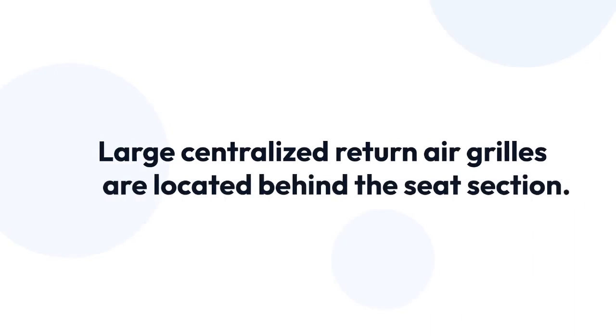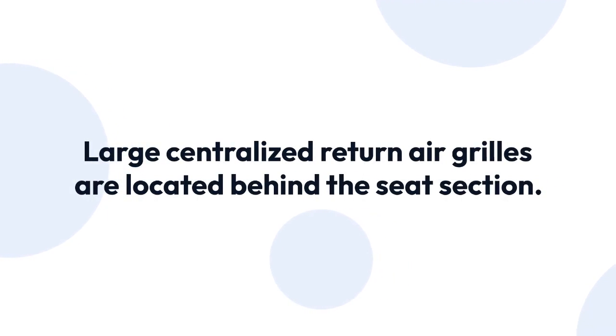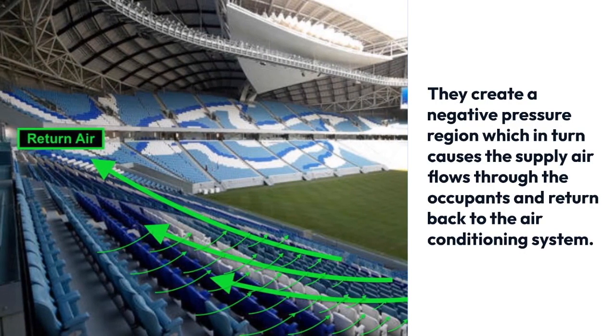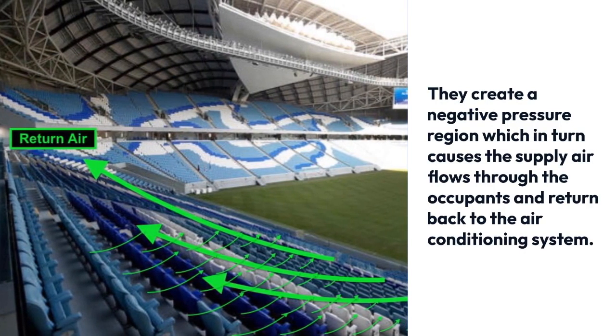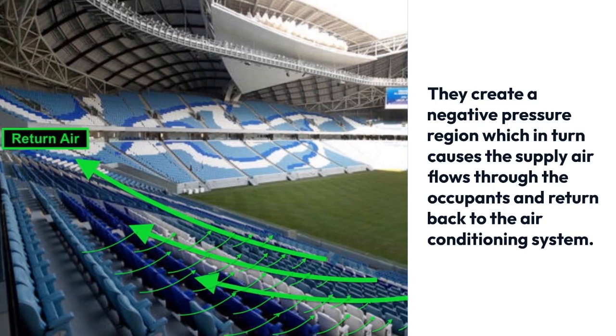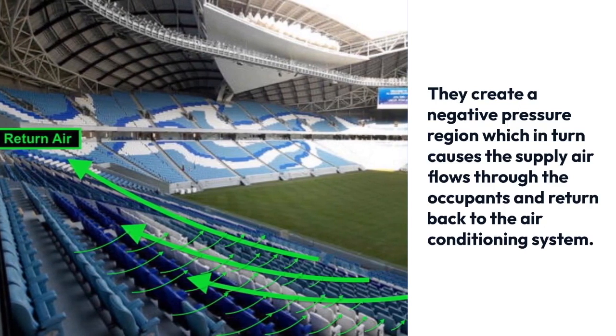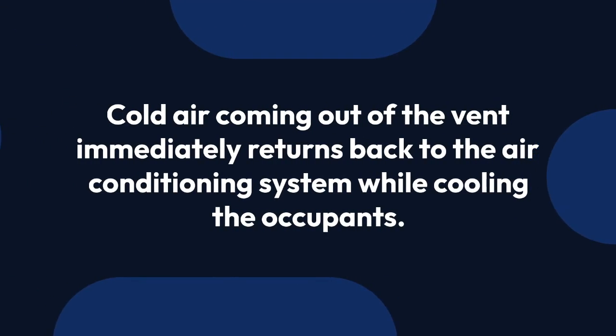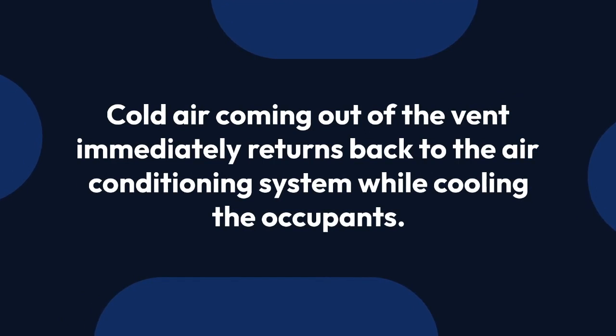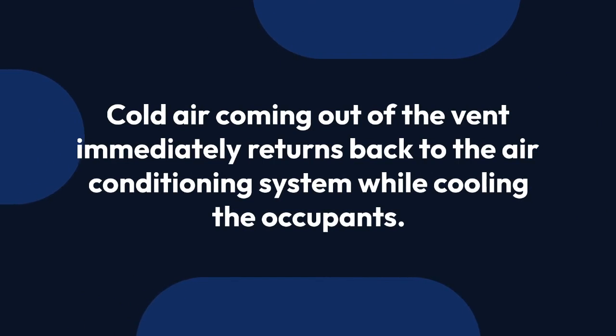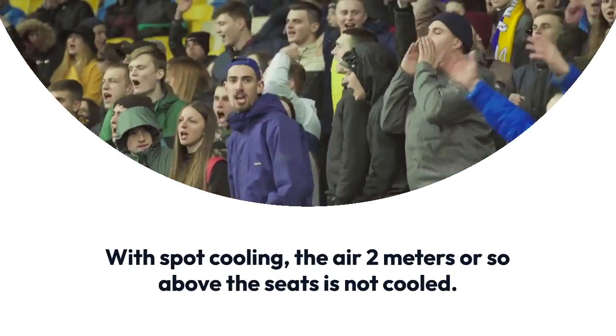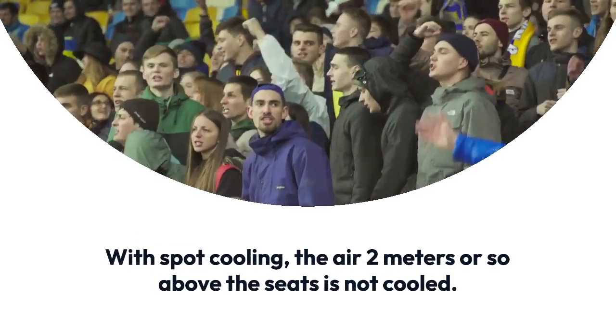Meanwhile, large centralized return air grills are located behind the seat section, or stands. They create a negative pressure region, which in turn causes the supply air to flow through the occupants and return back to the air conditioning system. Essentially, the cold air coming out of the vent immediately returns back to the air conditioning system while cooling the occupants. With spot cooling, the air 2 meters or so above the seats is not cooled.